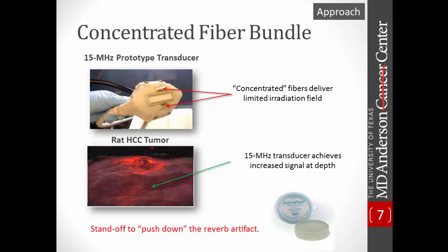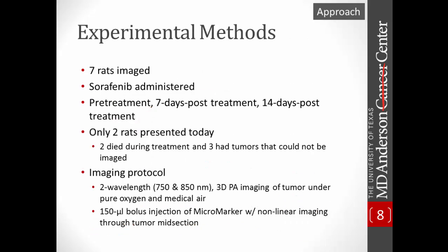And then coupled with that, we used a standoff, which turned out to be the game changer, because through this near field absorption, we get really bad reverb. This reverb artifact would often confound our imaging at the tumor site, so we could push the skin down at a fixed distance from the transducer face to try and mitigate that effect.